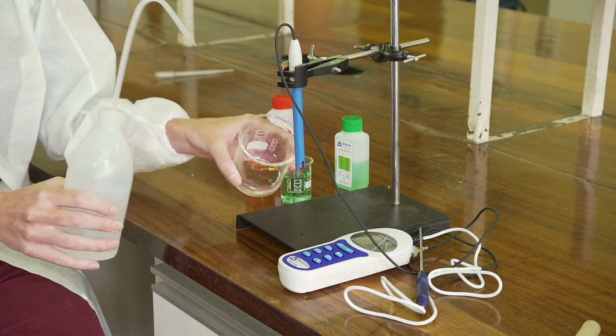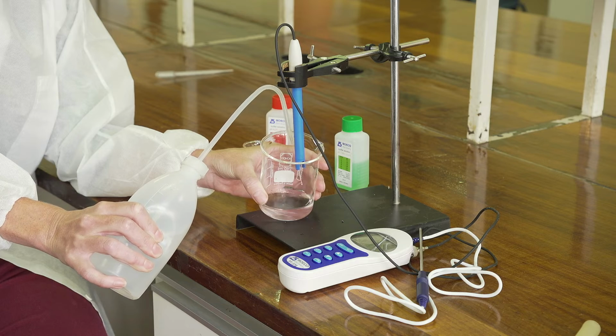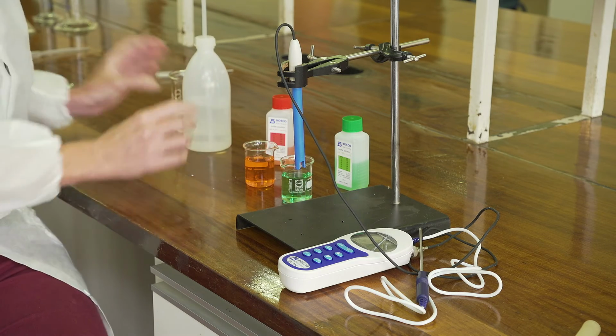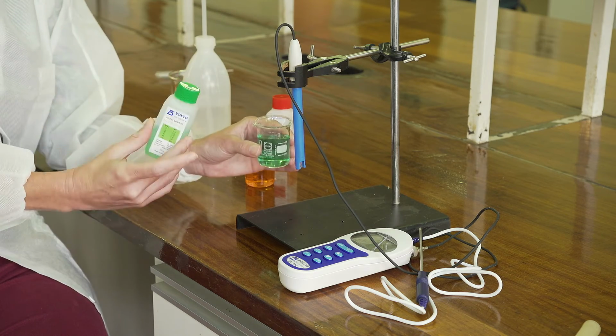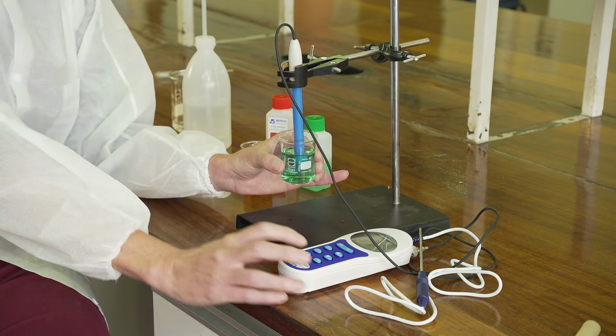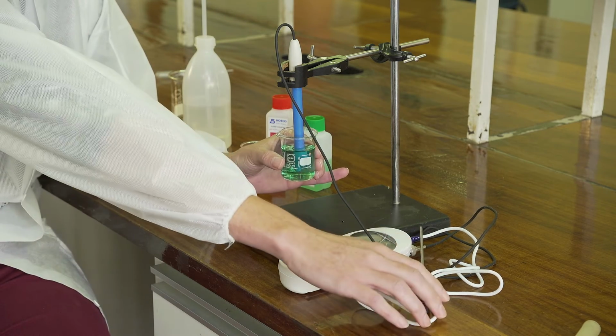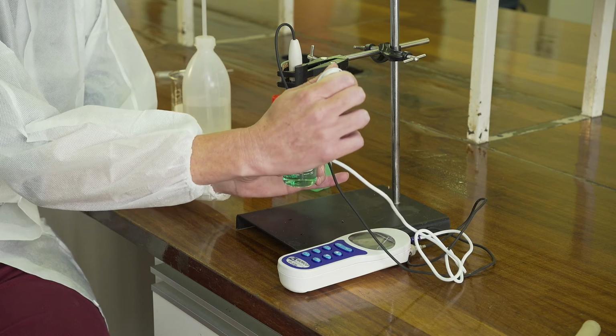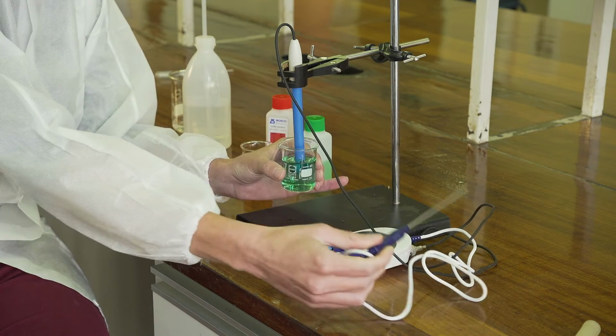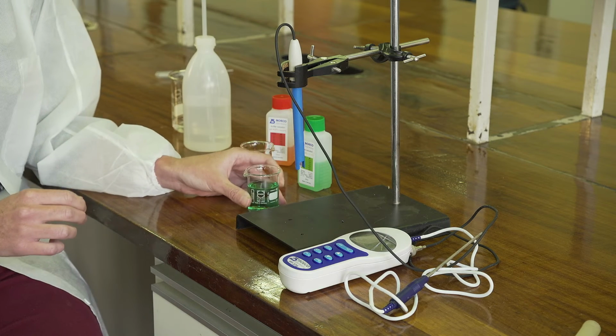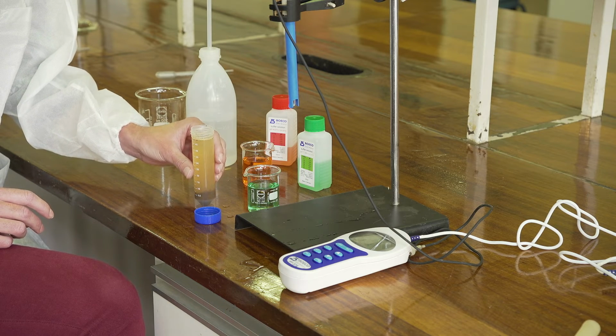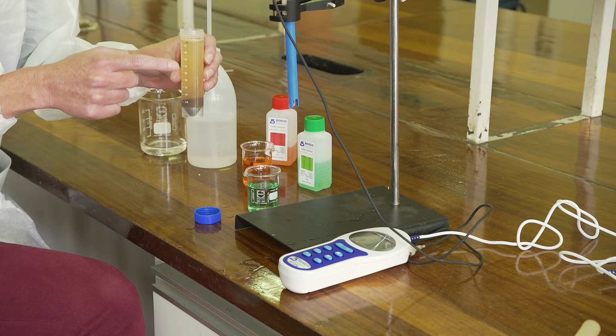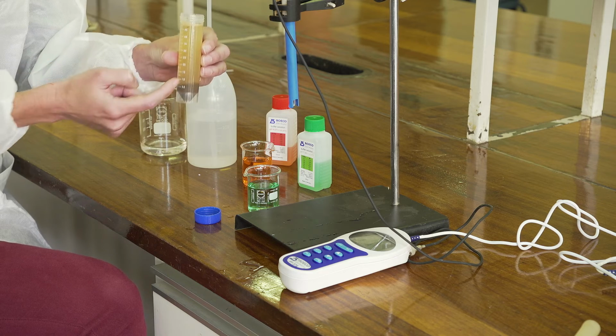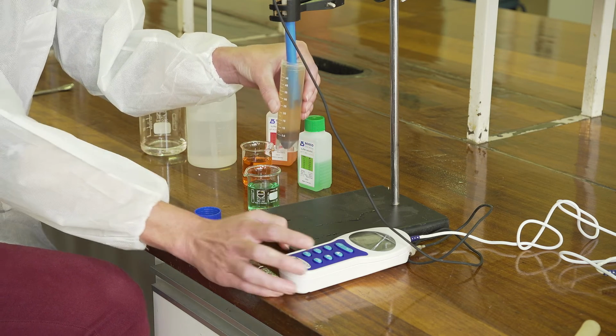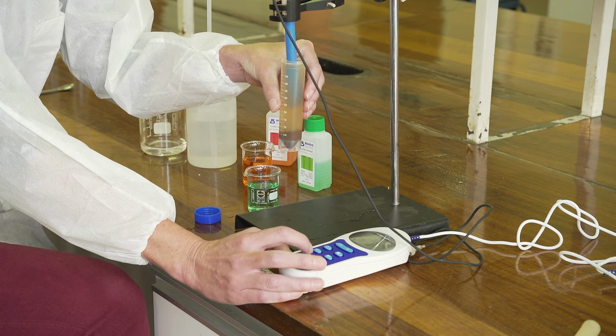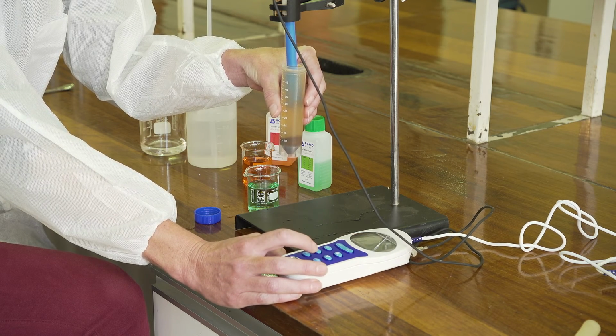Between the solutions, we have to clean it with the deionized water solution. Thereafter, we go on to the pH 7. 7.01. Similarly, we also correct for temperature. The sample is now back from the centrifuge, and it's now time to record the pH of the sample. We're going to be placing the probe into this clear part of the supernatant above the soil pellet at the bottom. It's fully immersed but not touching the pellet. And the reading is 5.82.